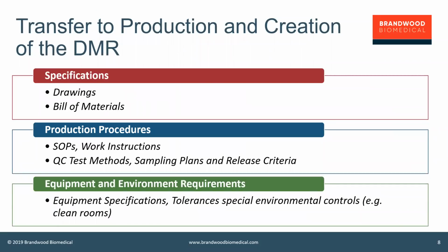That leads me to this next one, which is really the link between the DHF and the DMR. So as we talk about the creation of this DHF, we've really talked about the design and development of the product and how the inputs and outputs and the verification and validation activities have created a suitable medical device for manufacturing that will meet the intended purpose.